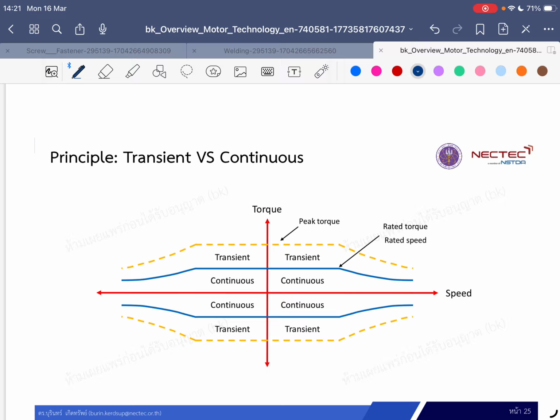Be careful, we need to see in more detail what is shown in the data sheet. Usually they don't show us the continuous power - I don't know why, maybe they don't want to share that. It's maybe 1/3 or half of the maximum power. Usually if you get a motor like 150 kilowatt, maybe the continuous power is only 70 or 50 kilowatt, something like that. So be careful when you read the motor data sheet.